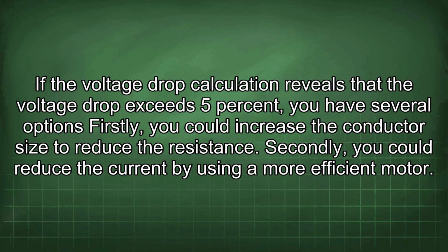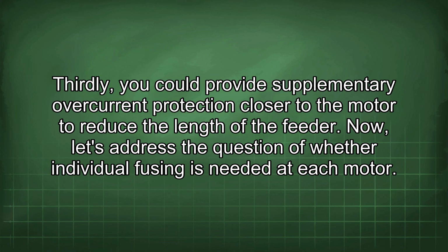If the voltage drop calculation reveals that the voltage drop exceeds 5%, you have several options. Firstly, you could increase the conductor size to reduce the resistance. Secondly, you could reduce the current by using a more efficient motor. Thirdly, you could provide supplementary overcurrent protection closer to the motor to reduce the length of the feeder.